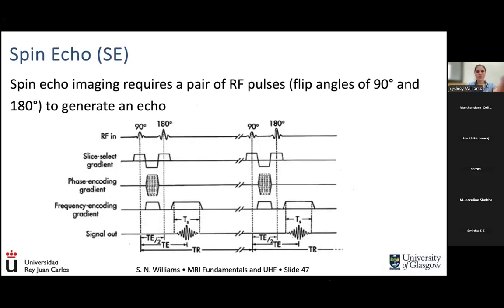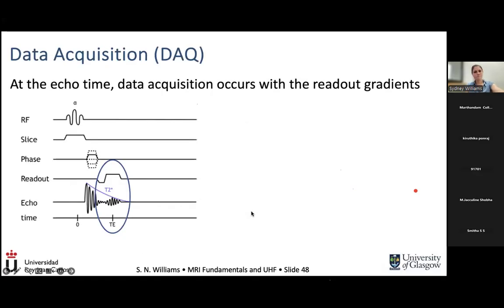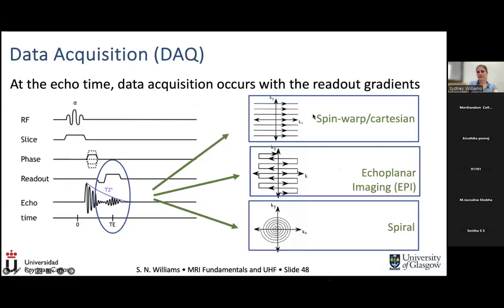Finally, in all of these scenarios, we have our RF pulse and then we have the point at which we're doing data acquisition. In the data acquisition part, we have different ways of actually using our gradients to really quickly acquire that data. At the echo time, you might think of just acquiring data line by line, and that's quite usual, but it's not really the most efficient way to collect data fast. So you could do data line by line in a Cartesian fashion shown here. Or you could be a little bit more creative and do things in a zigzag back and forth through every line phase. So every single time we collect an echo, we collect a full 2D slice, and that's called echo planar imaging. It's really popular. It's also known as EPI.